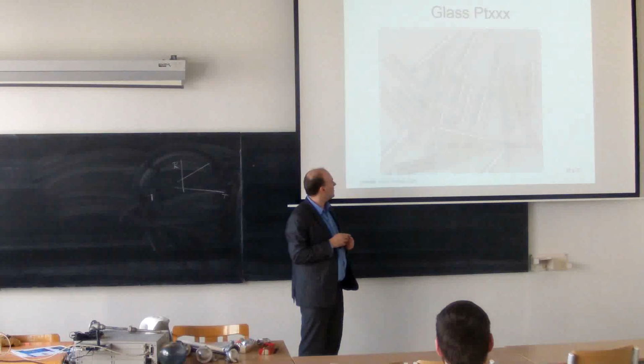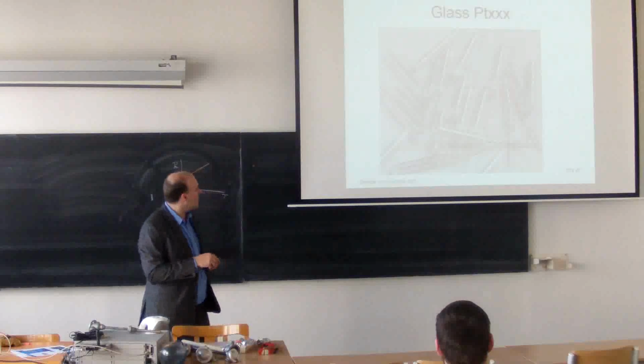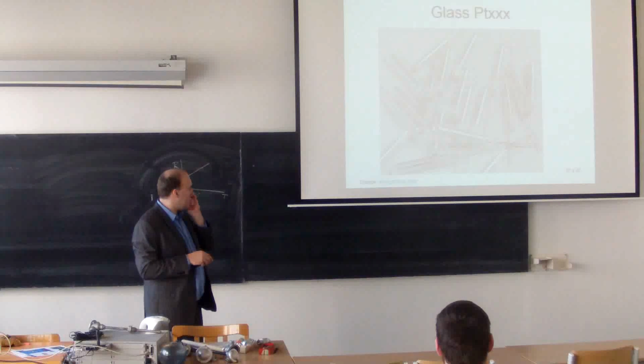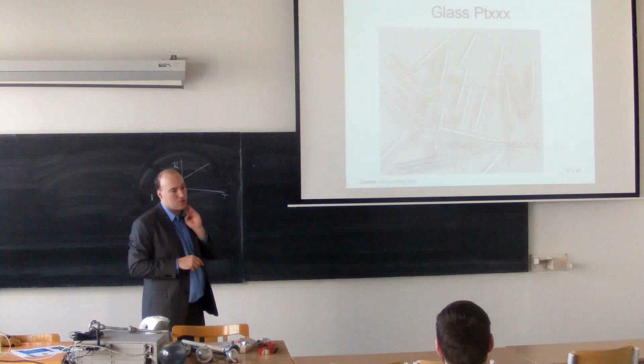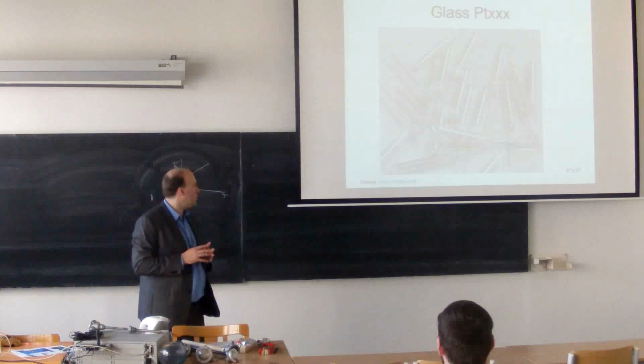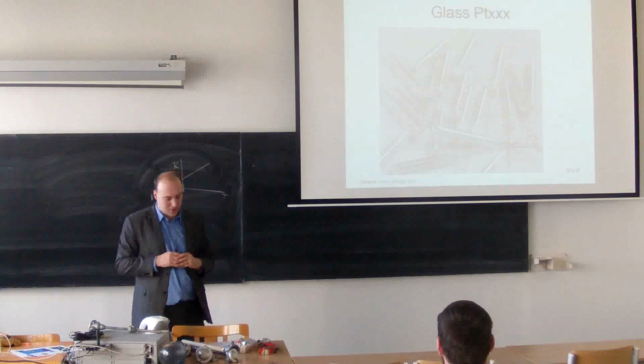It looks something like this. It's like a rod, as you can see directly the platinum wire inside. And due to the glass that is used here, it can be used up to 600 centigrades approximately. That's the maximum temperature.